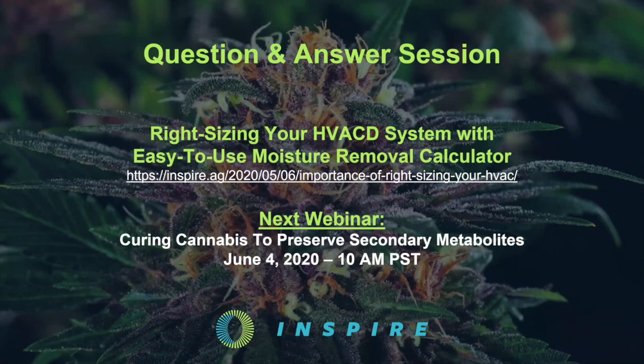And Brian, I'd like to add a little something too. Back when we were doing work in the mushroom industry, large soil beds were kind of the de facto standard for growing mushrooms inside of a cold, wet, dark room. And so maintaining those bed temperatures was pretty important. And some of the methods they use there, and I've seen some of this in the cannabis industry, people attempting it anyways, would be to use basically coiled piping, a radiant floor type system underneath the bed. You could put cool or hot water through it and end up with a temperature control scheme that way.